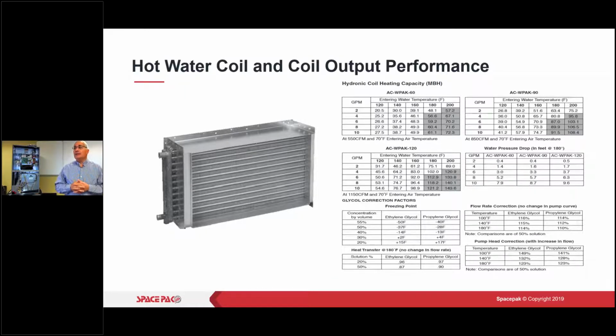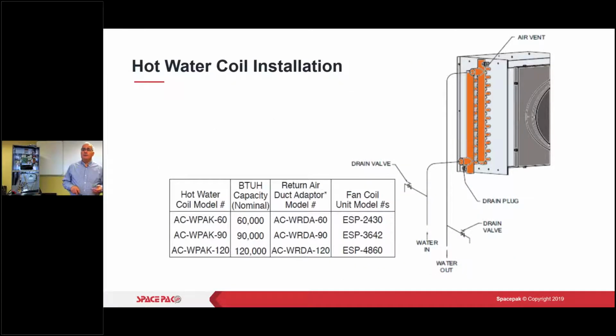Real important too when you're sizing this out, if you're going with GPM and you're not going to go with copper but with PEX pipe, that you size that properly. Inside diameter of PEX is smaller than copper. Let's say I have to move 8 GPM. In copper you would think 1 inch copper, that's going to be 1.25 PEX. If you're in that 3/4 range of 4 GPM copper, that's really going to be 1 inch PEX. So be aware of that. You don't want to pre-run your lines and then realize you have to change that later.